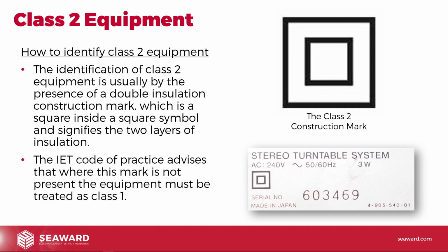The IET Code of Practice advises that where the mark is not present, the equipment must be treated as class 1. So what they're saying is if you can't identify whether it's class 1 or class 2, always treat it as class 1. Now obviously if you treat it as class 1 and it is class 2 equipment, it's going to fail the earth continuity test. But what they're saying is it's better that it fails and then maybe you go back, speak to the manufacturer, do some more investigation, than just assuming it's class 2 when actually it might be class 1 with dodgy earth. So they're saying to be on the safe side, if you can't identify it, treat it as if it's class 1, and obviously if it passes the class 1 test, then you know it was actually class 1.